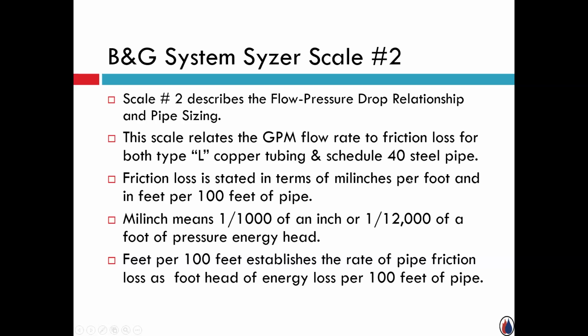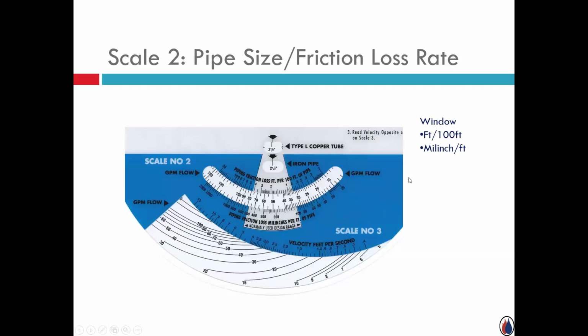Right here at the very bottom, feet per 100 feet, that's what we're going to reference. That's what we use. We talked about it last week when you look at pump curves. They're listed in feet of head per 100 feet. And so you look at Scale 2, pipe size, friction loss rate. So we're trying to establish what size pipe, whether it be Type L copper or iron pipe, in this white band here is the flow rate, listed in gallons per minute. And that top side of it is saying, hey, this is the piping friction loss in feet per 100 feet of pipe.